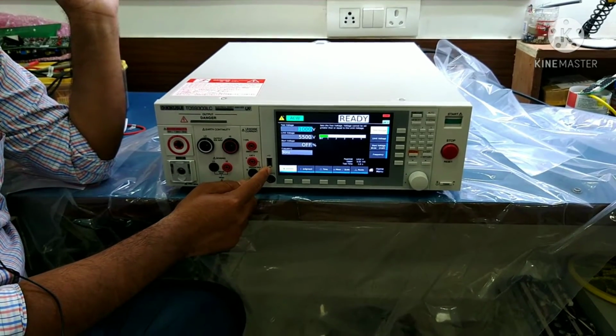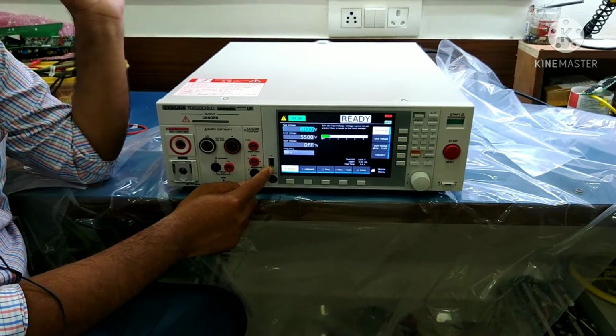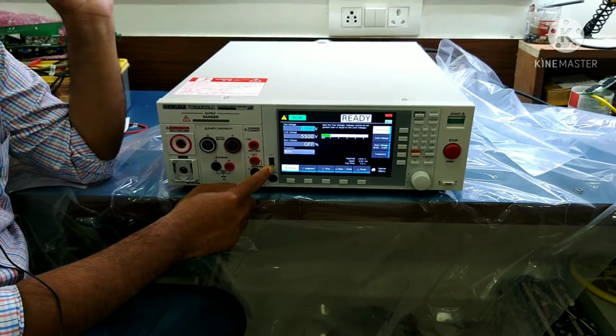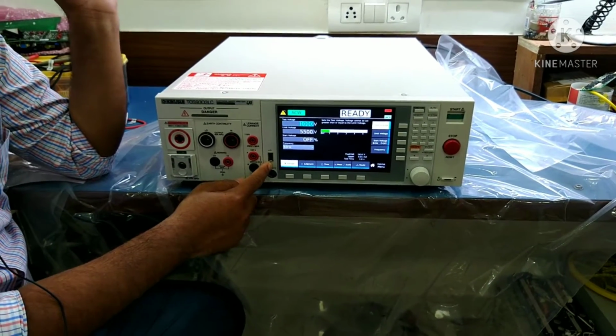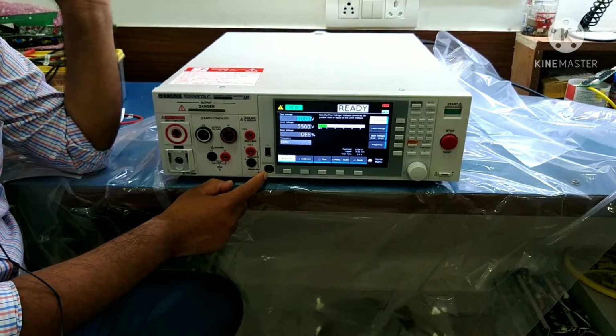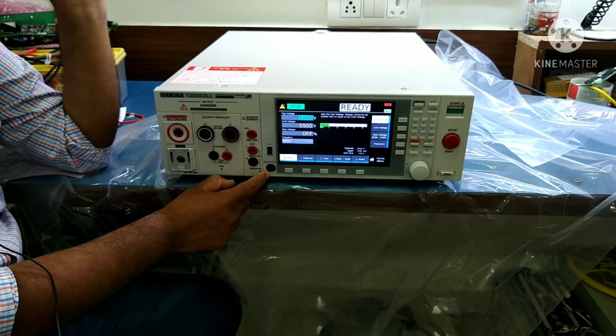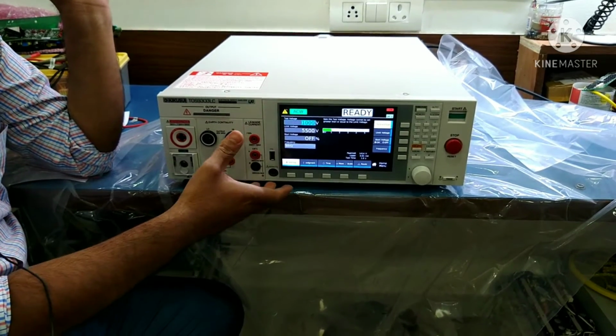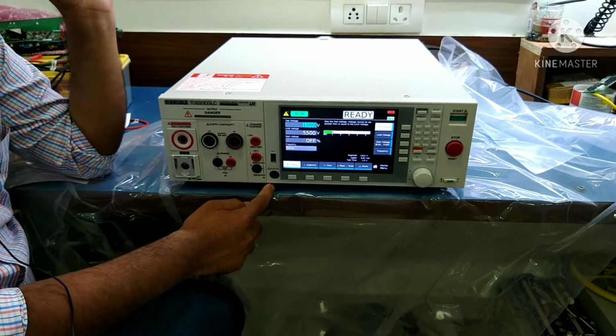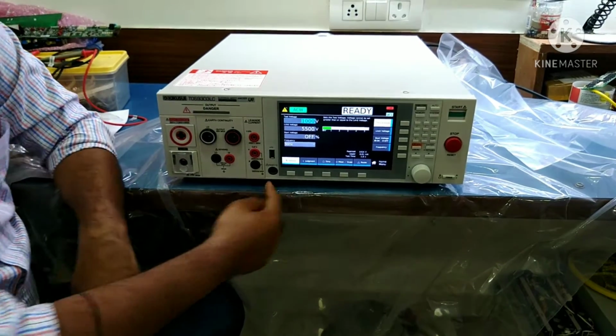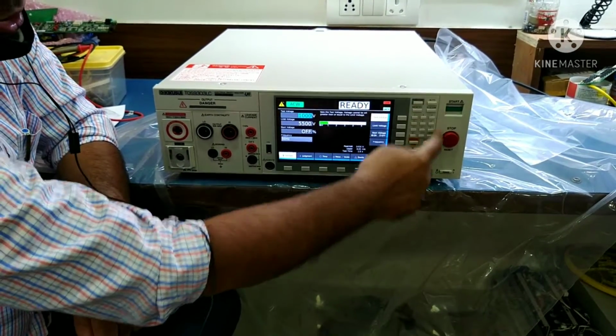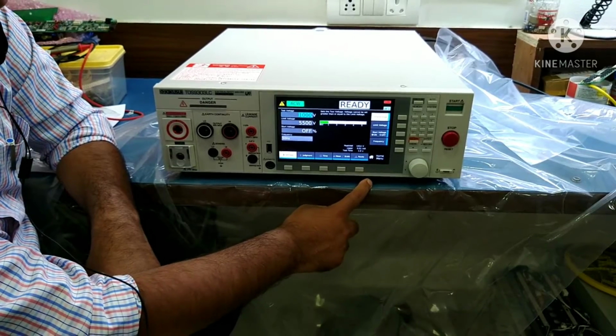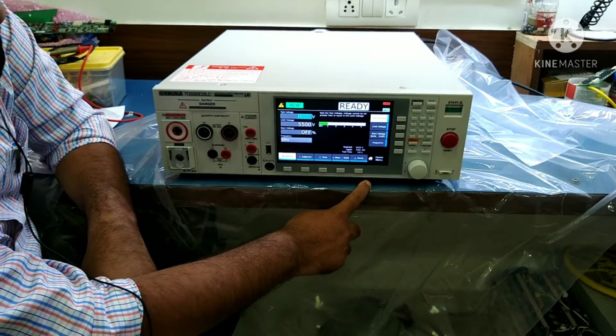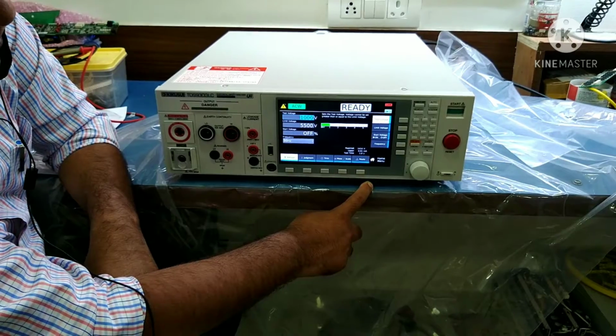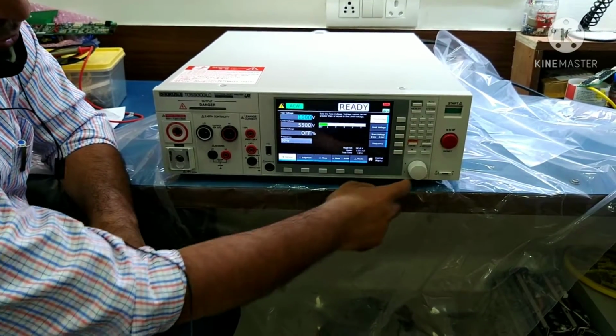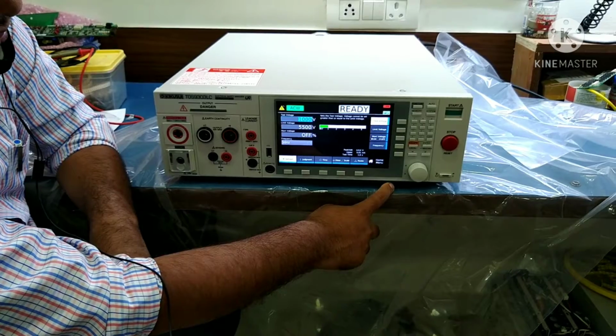And this is used for saving the data in an external storage device like a USB pen drive. This is a remote function, which is basically provided for controlling this instrument through an external start-stop switch. These are the function keys, so we can change all the data like setting the voltage, current, timers, and also use them for making programs, auto programming of the auto testing.